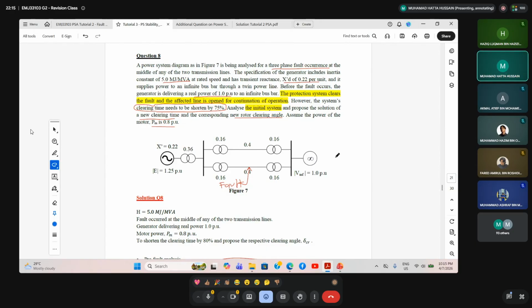Okay, for question 8, we have a 3-phase fault occurring in the middle of this transmission line. We have the inertia constant, which means the kinetic energy stored in the rotor, 5 megajoule per MVA at rated speed. We have the transient reactance Xd prime, j0.22 per unit, and the real power P equal to 1.0 per unit to an infinite bus bar. The protection system clears the fault and the affected line is open for continuation of operation. However, the system clearing time needs to be shortened by 75%. Analyze the initial system and propose a new clearing time and the corresponding new rotor clearing angle. Assume that the power of the motor PM is equal to 0.8 per unit.